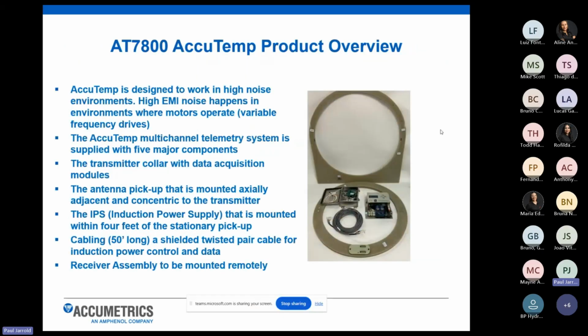So this is what the AT7800 AccuTemp system looks like. It's, again, designed to work in very high noise environments that have a lot of EMI, RFI noise. We don't have to worry about any variable frequency drives or pony motors or lube oil pumps that are operating in and around that motor. Our system is immune to any of that electrical noise. We provide you with 8 channels of RTDs, and it's made up of these 5 main components: the transmitter collar, the antenna pickup, the induction power supply, and the cabling to connect that then to our receiver assembly.